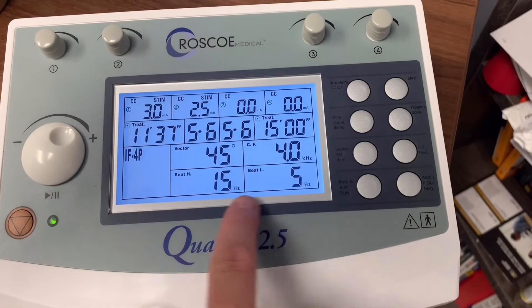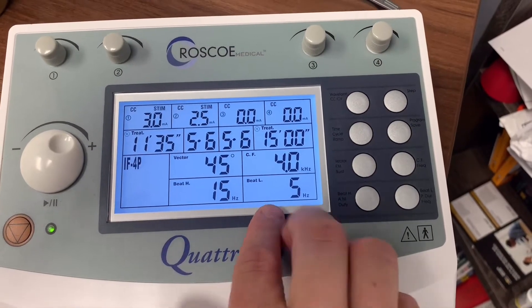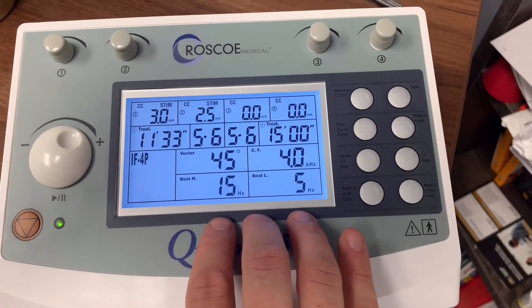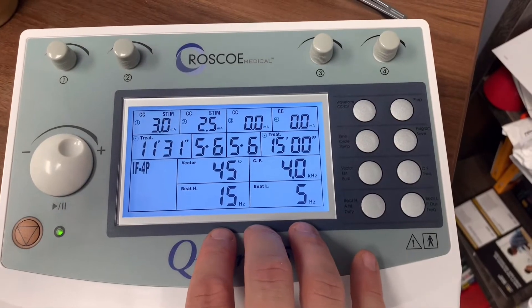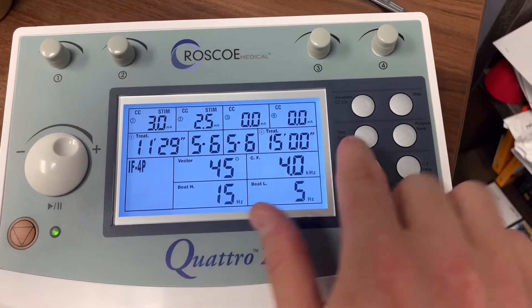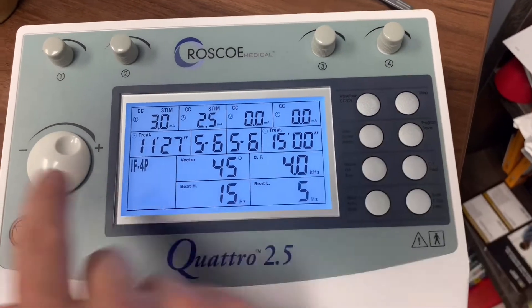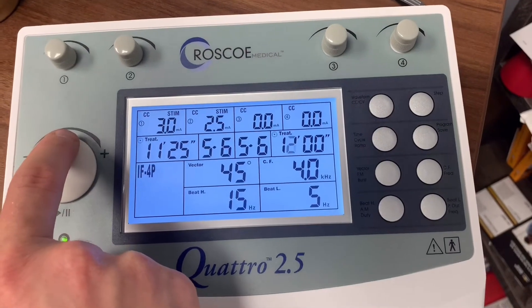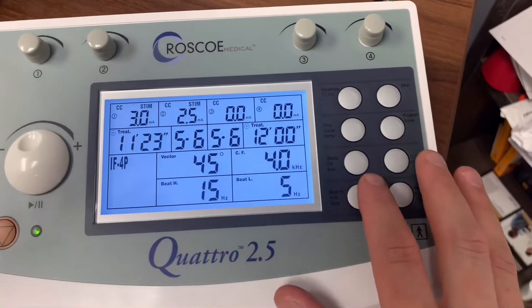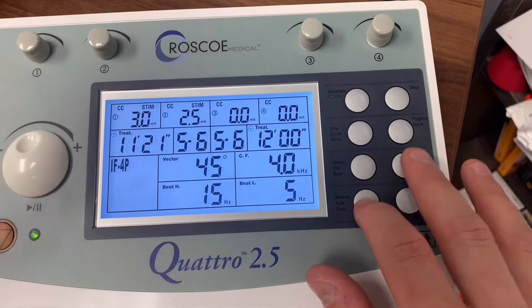And then we're going to adjust because right now you can see it is not running the same setup that we had for channels 1 and 2. You can see the treatment time is not correct, so we're going to change that. We're going to go down to 12 minutes like we have set up for the other.